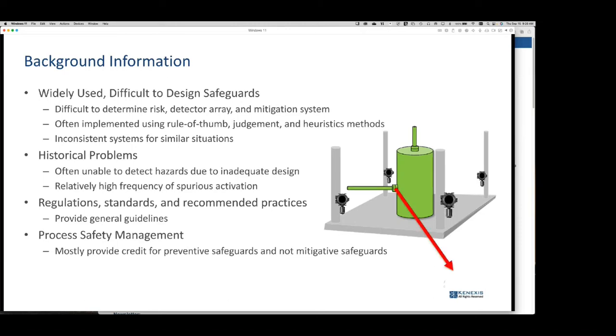And then lo and behold, they had a gas leak one day, and none of those brand new shiny detectors alarmed. The engineers just stood there going, well, the old detectors we had in the facility all went into alarm, but these new ones didn't alarm. So take the new ones out and put the old ones back in. And they called the people who had sold them the detectors, and helped them out with the process, and have been very helpful.